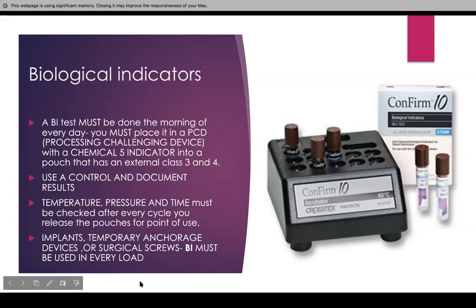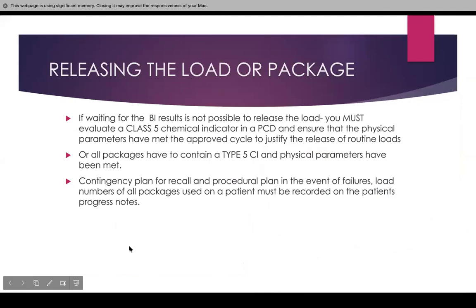For implants, temporary anchorage devices, or surgical screws, biological indicators must be used in every load. Regarding releasing the load — if we are waiting for the BI results, it's not possible to release the load immediately, but you can and must evaluate the class 5 chemical indicator placed in the PCD. That is why we always say you have to place the PCD every morning with a class 5 indicator and the BI. You release that so we are sterilizing throughout the day. We still have to place the PCD with a class 5 chemical indicator for every cycle to justify the release of routine loads.